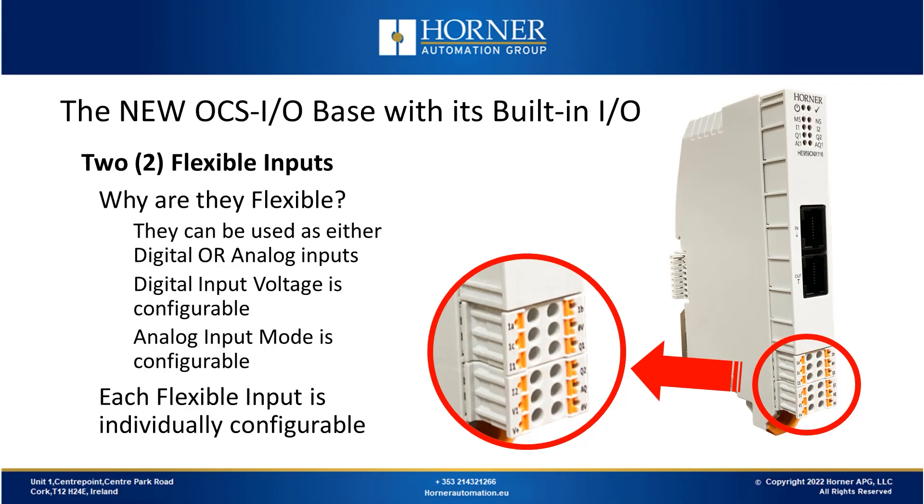We'll start with the two flexible inputs. They're flexible because they can be used as either digital or analog inputs. If you're using them as a digital input, the input voltage used to turn on when the switch triggers is also configurable. If you're using them in analog input mode, you can configure them between different signal types. The two flexible inputs are independently configurable, so one could be used for analog and one for digital, or both for analog or both for digital, depending on what you're looking for.